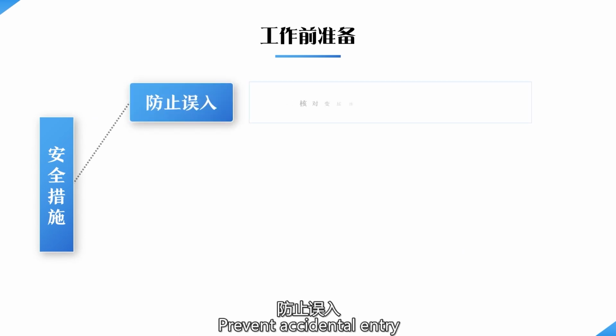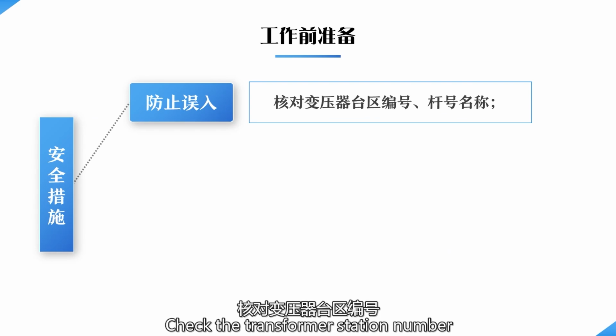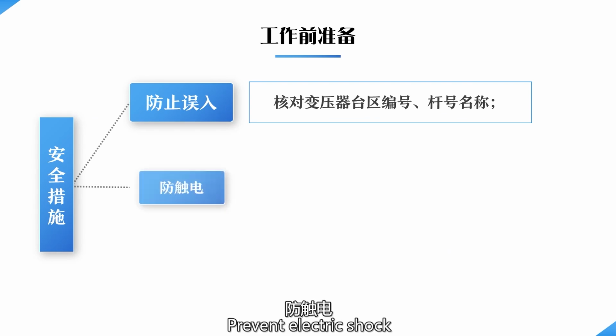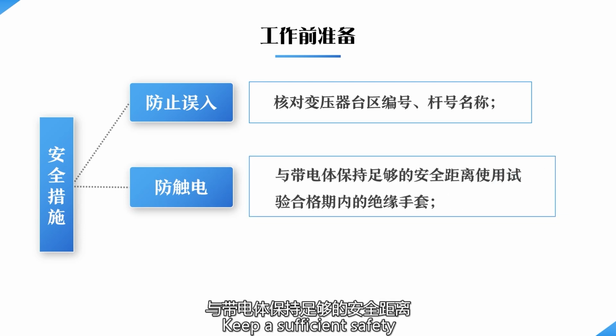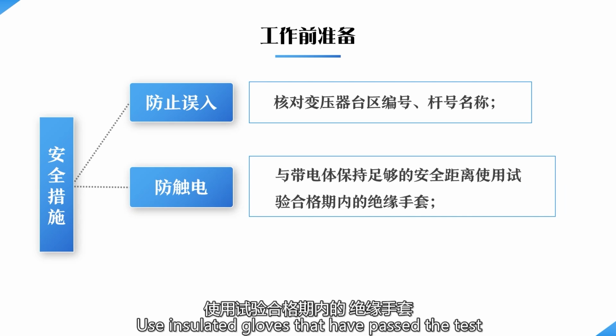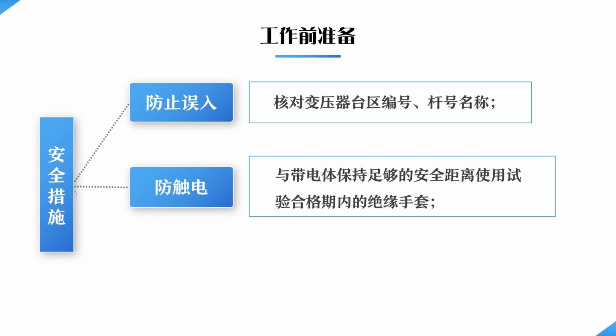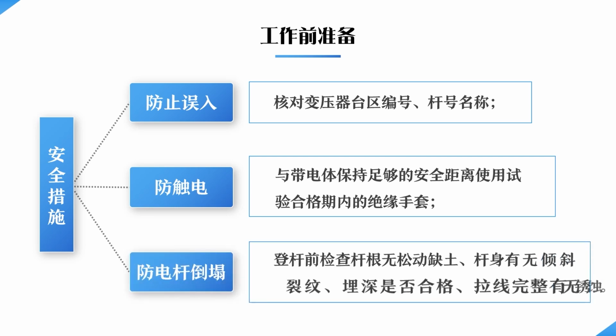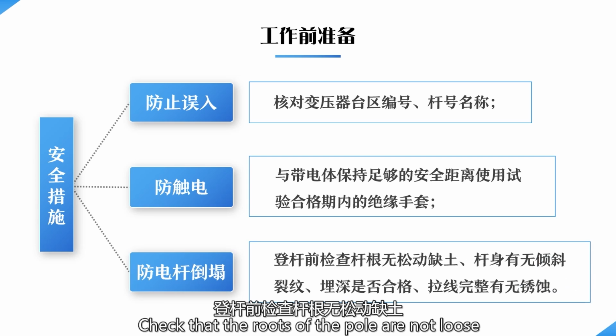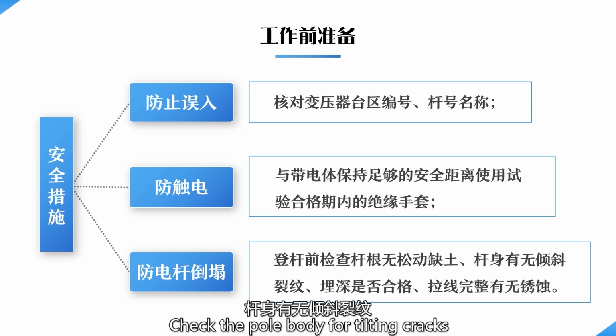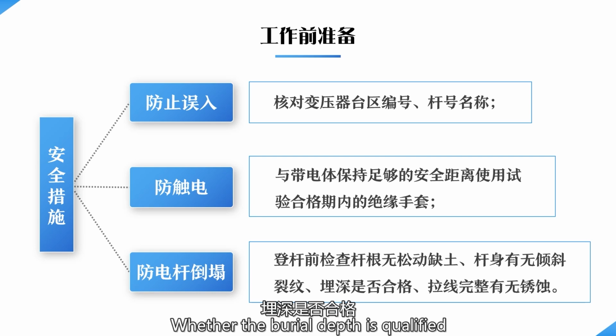Prevent accidental entry: check the transformer station number and pole number name. Prevent electric shock: keep a sufficient safety distance from energized bodies, and use insulated gloves that have passed the test. Prevention of pole collapse: before climbing the pole, check that the roots of the pole are not loose and do not lack soil. Check the pole body for tilting and cracks, and whether the burial depth is qualified. Tie wires should be intact and not corroded.